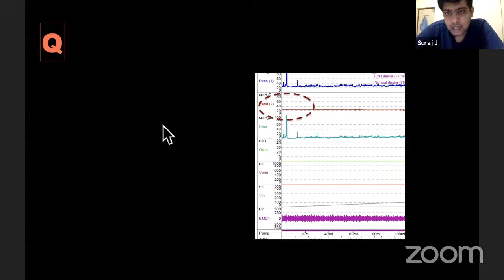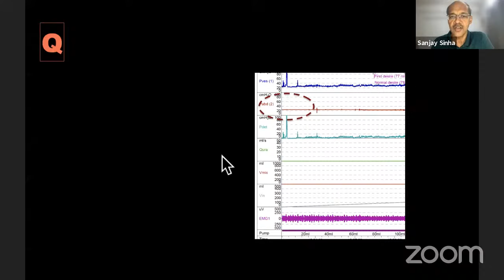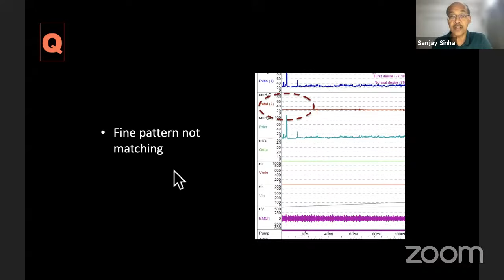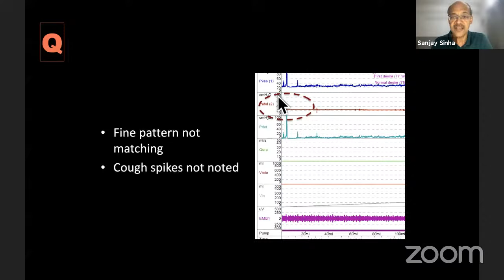Right. So as Suraj rightly pointed out, the abdominal channel is not recording. So when you do this initial cough, you find that the cough is completely seen on the PDET when it should not be, because it's not something generated by the detrusor wall, because there is no recording on the P-abdomen channel. So in this patient, the fine pattern you can see is not matching. So you can see here, this is a fatal flaw. If you have this kind of thing happening, you just cannot interpret the study later. The cough spikes are not noted in the abdominal pressure channel. The fine pattern is not matching. You need to recheck the rectal catheter, flush, check the connections and start again.